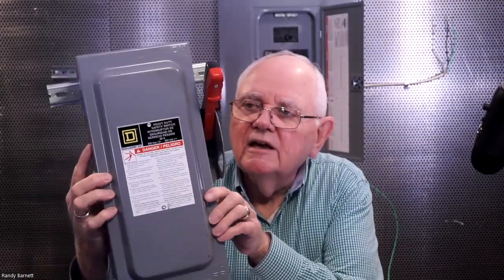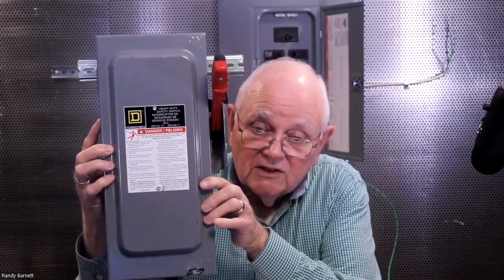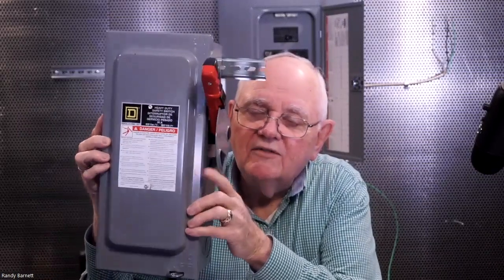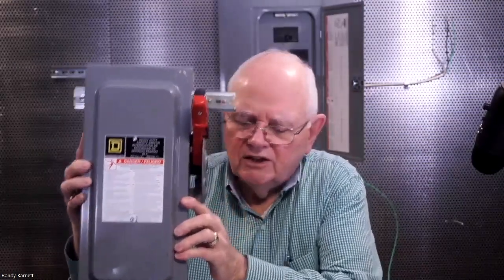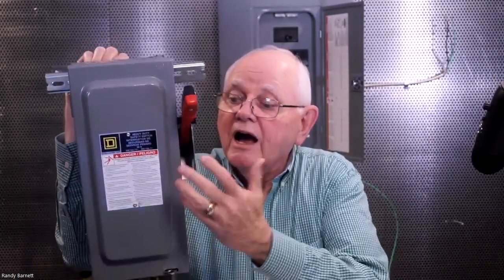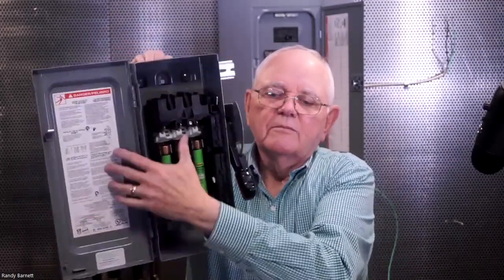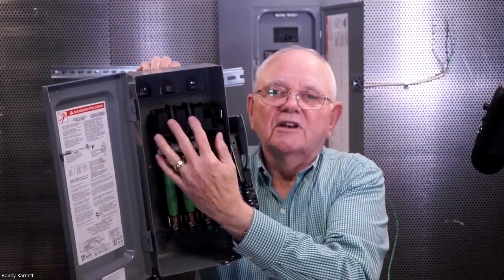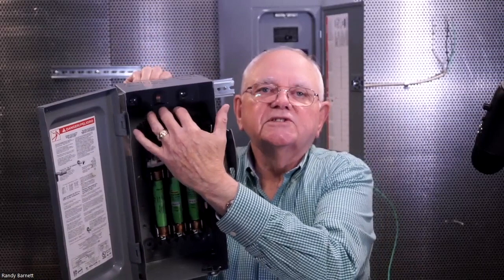Now, another thing we have to be concerned about with refrigerating equipment is access by unqualified people. So we've got to make sure that there's some kind of interlock. For instance, when this handle is in the up position, I can't open the door. Also, I'd be able to put a lock on, which I could right here, and prevent anybody from opening the door while the equipment is running, while the disconnect is energized. Now, one thing to keep in mind: let's go ahead and shut the power off. We open up. Remember, top is always hot, right? I still have incoming power to the top of these stabs.